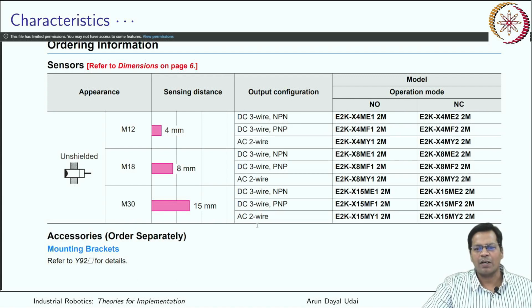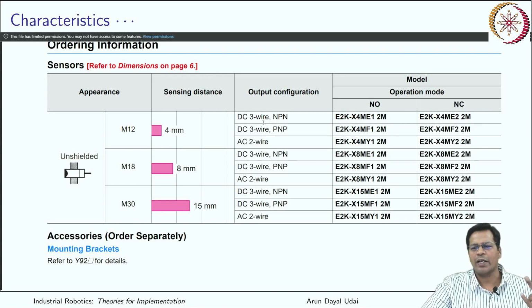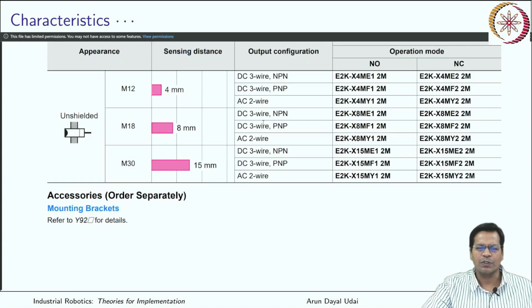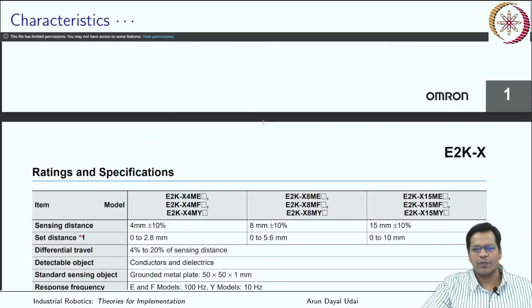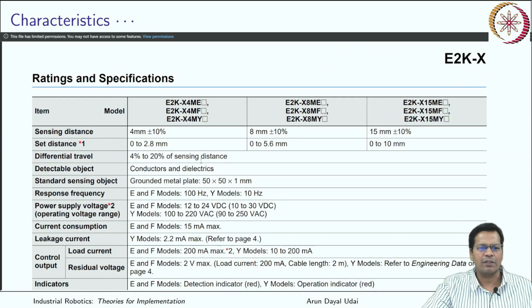All of them are 3-wire kind, can be PNP or NPN type. So 3-wire basically, output is just one, two of them are supply, so 0 and maybe 24 volts, and output is in the range of, because it is digital in nature, 0 or 24 volt or 0 or 5 volt, depending on the type of device.